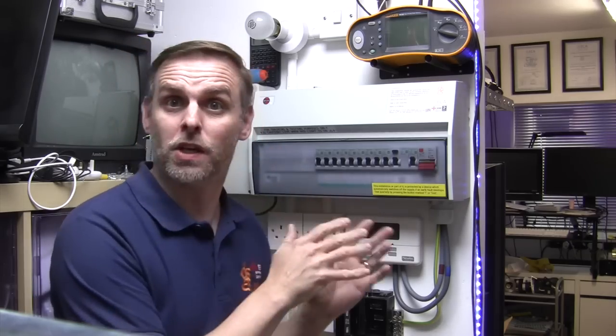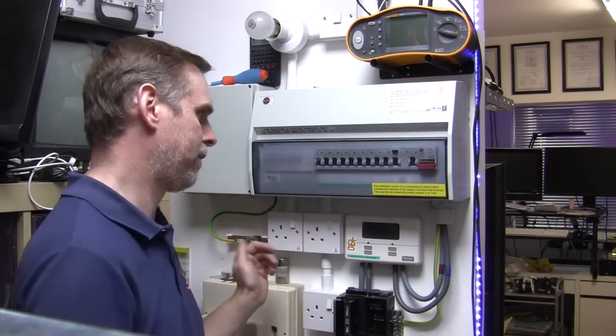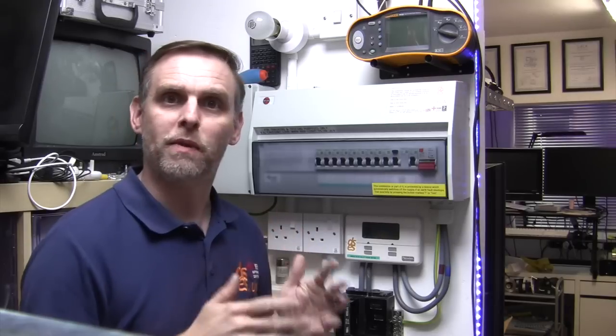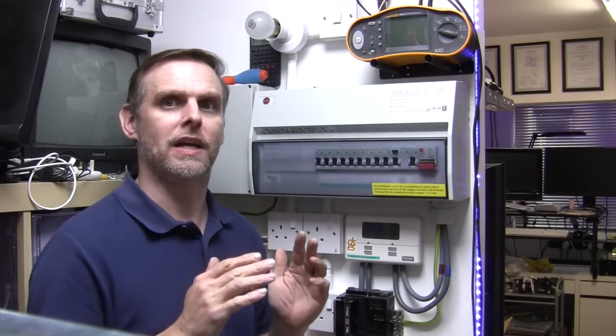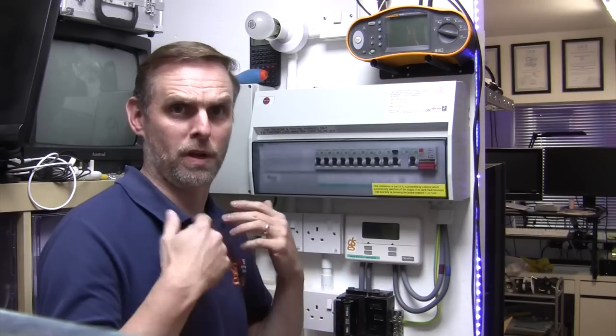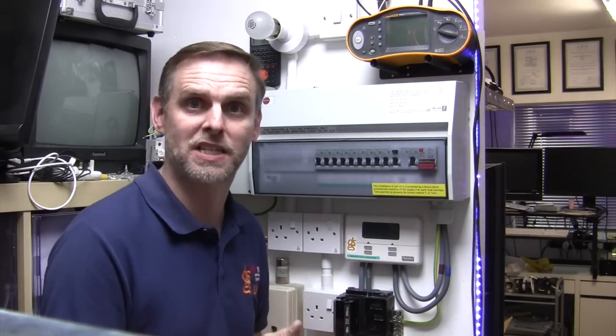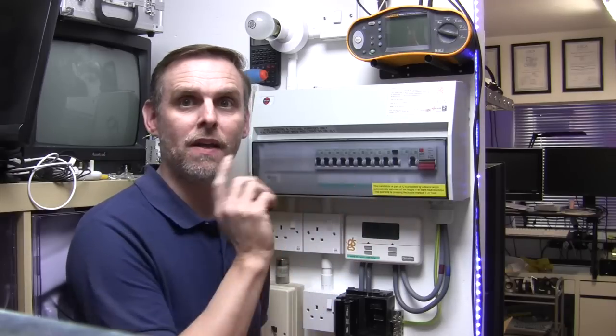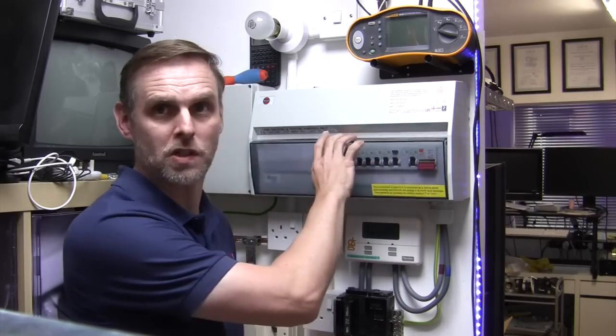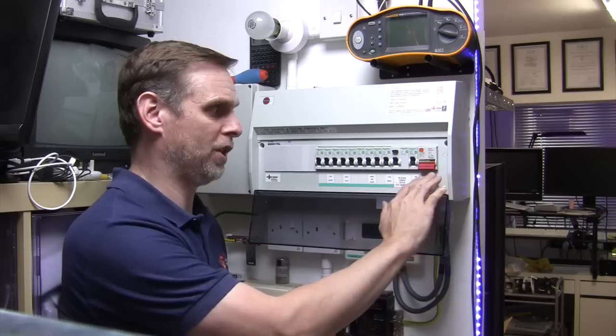I've identified the circuit that I'm going to be working on, so I know which breaker it's on, and I've got permission to turn it off. However, if you're doing a competent person's assessment and you're demonstrating your knowledge of safe isolation to your assessor and you're at the consumer unit, then you must seek permission to turn off not just the circuit you're working on, but the whole consumer unit.